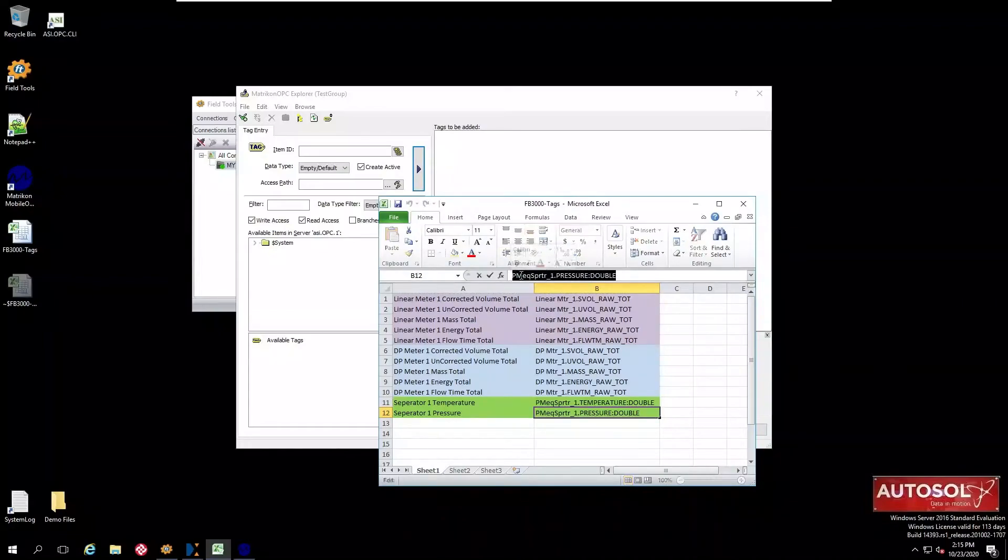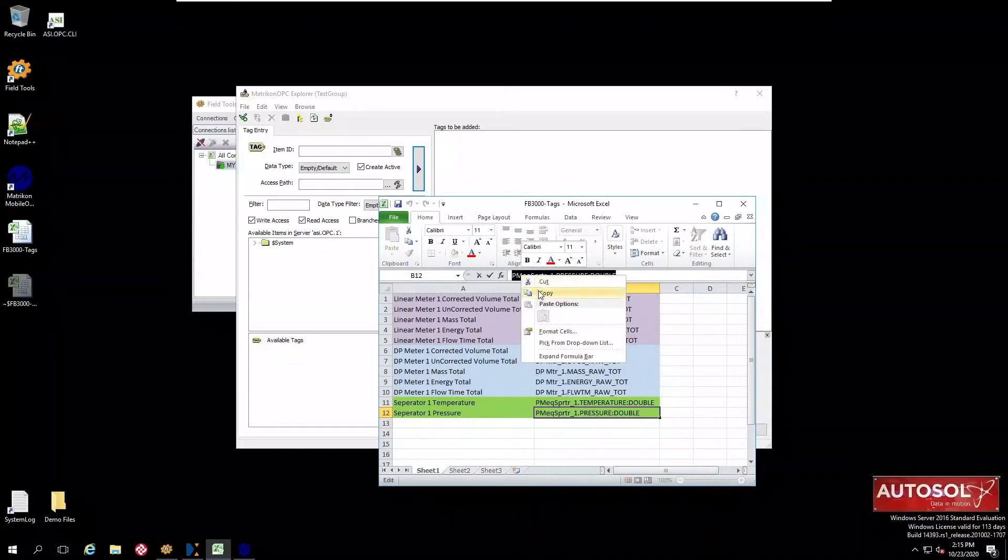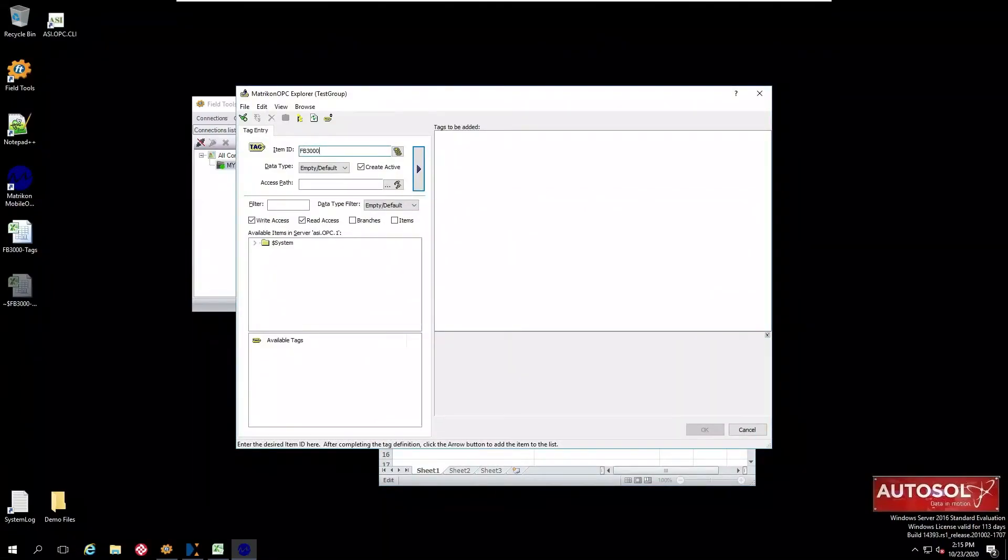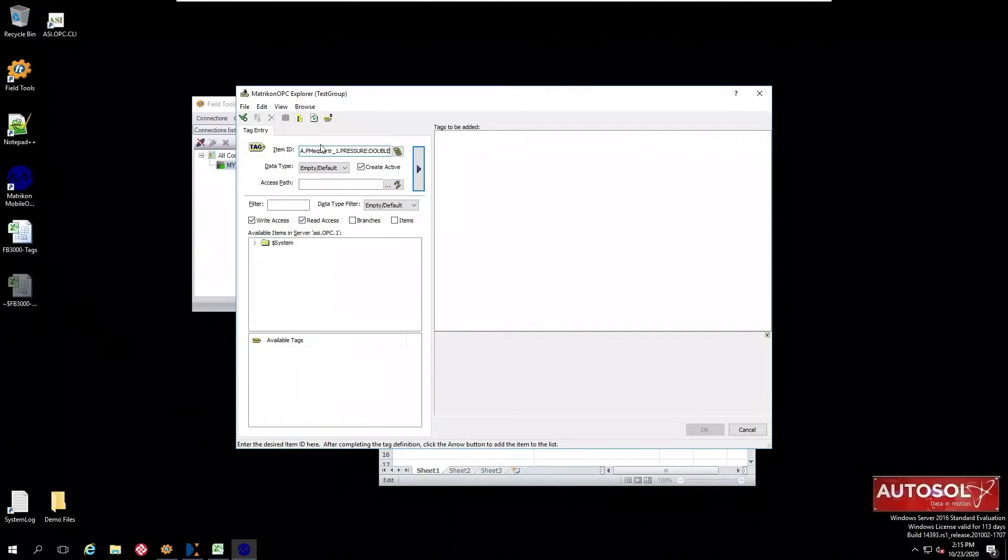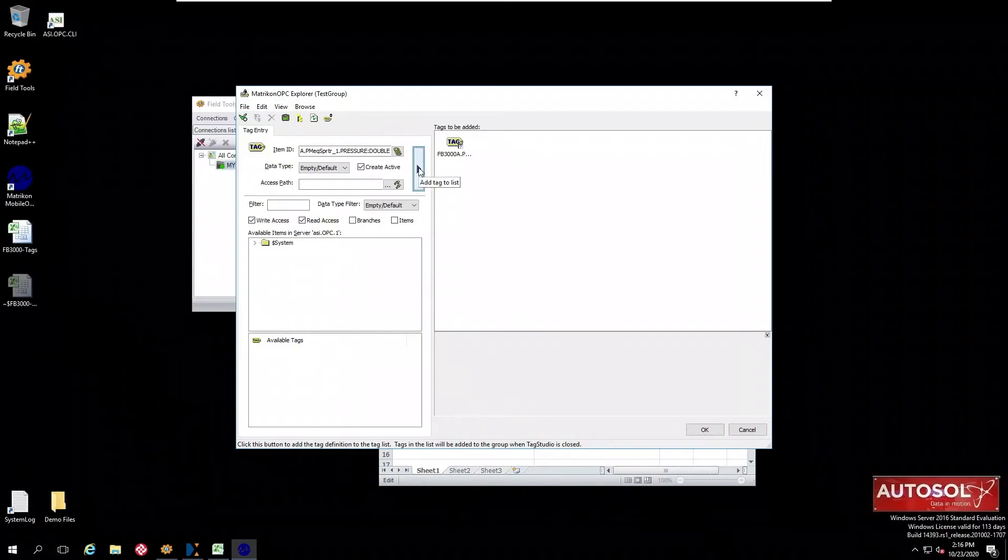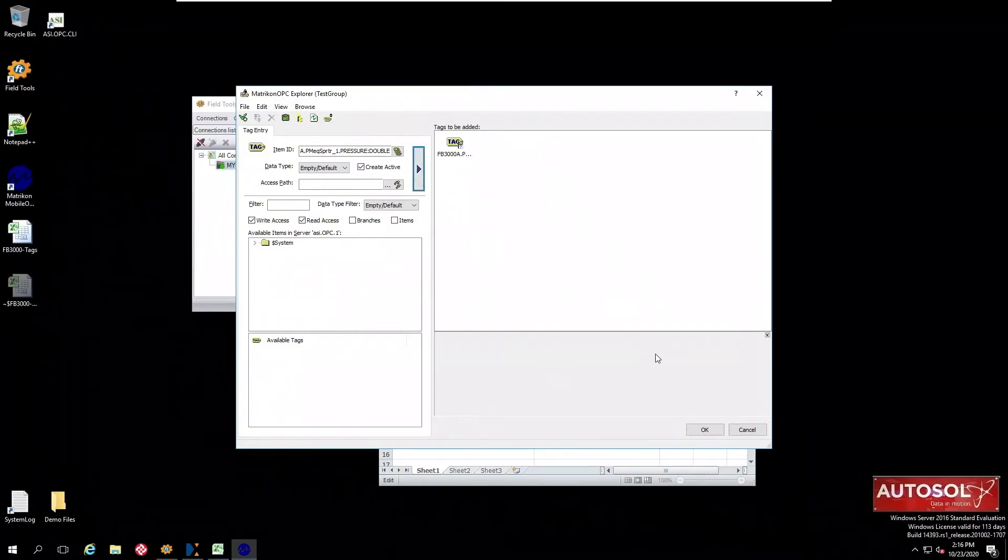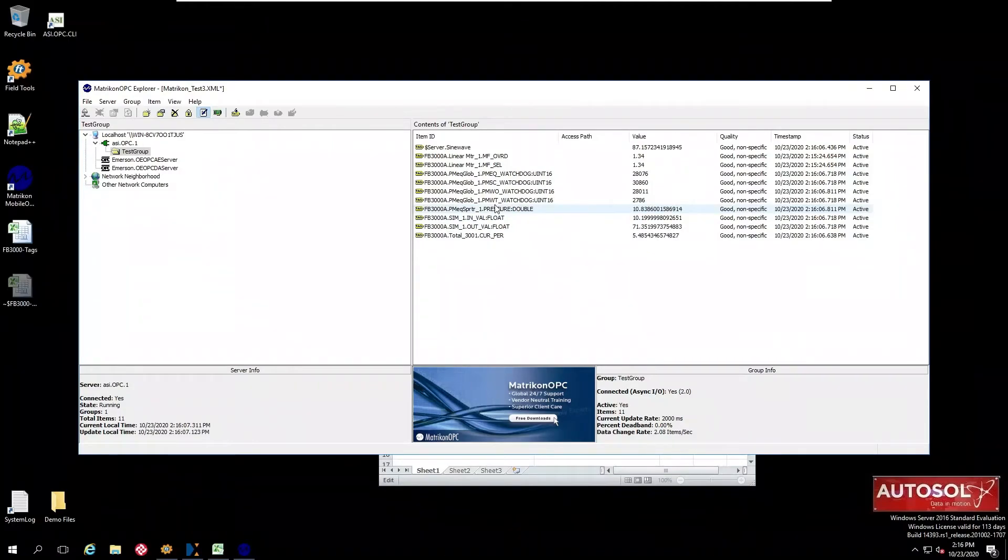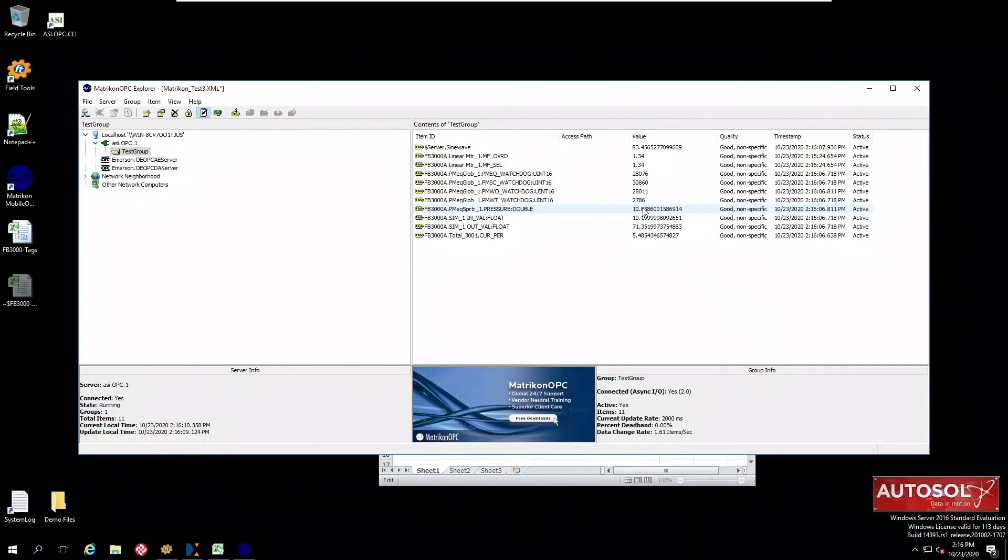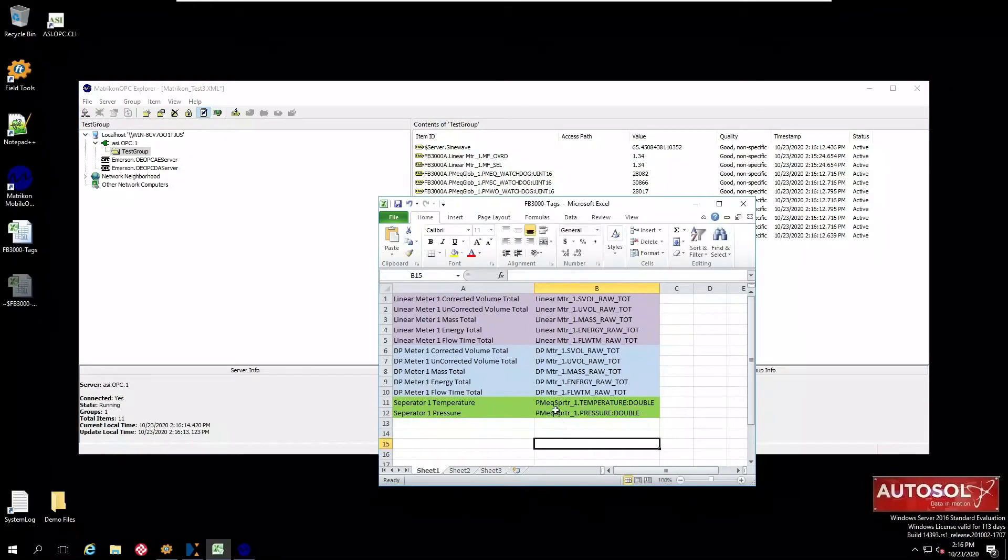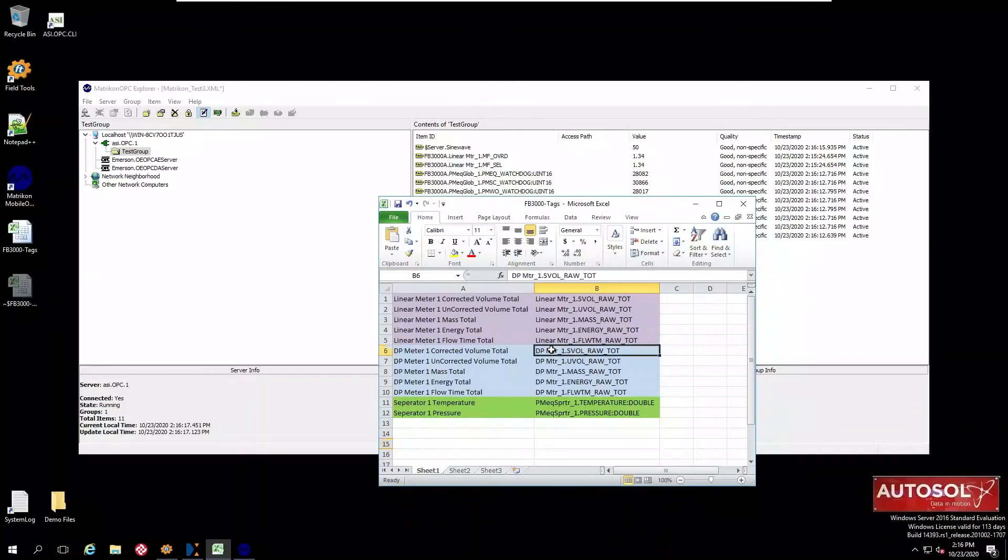First let's take one of the separator values and copy the tag name carefully because again it is case sensitive. Now first we need to put the RTU name in which is configured within Autosol, that's FB3000A, and then paste the tag name after it. You may notice that for a user defined tag you add the data type, that's double in this case, on the end and you can see we have the live value coming in from the RTU.